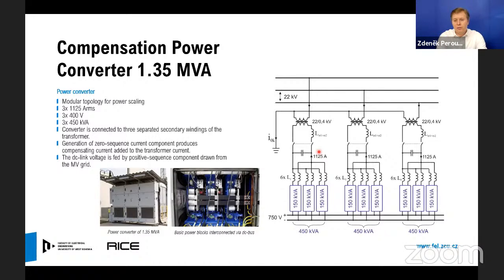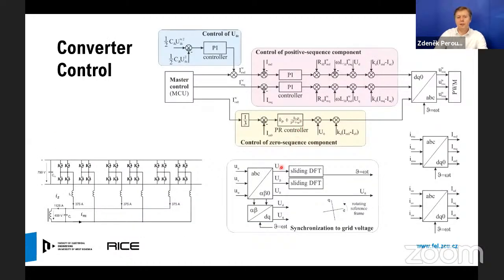Just a brief idea of how our converter looks. It is a three-phase converter where we are using a modular topology with fundamental building blocks with the rated power of 150 kVA, which makes easy scaling of our device possible. In our prototype we are operating three fundamental building blocks in parallel, and they are connected via an LCL filter to a secondary winding of the converter transformer. A few words about the control. We have several control modes. Positive sequence components are controlled in the rotating reference frame DQ, which is linked with the grid voltage, while the zero sequence component is controlled by a proportional resonant controller.